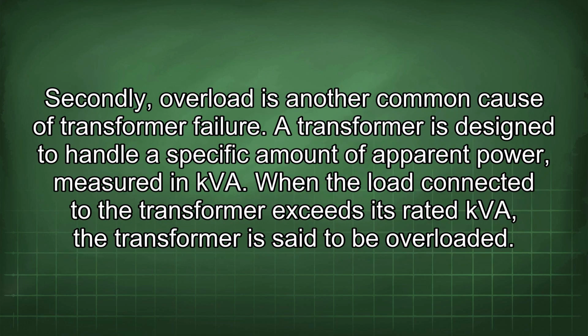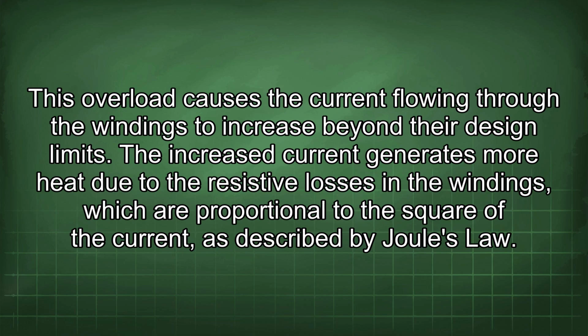Secondly, overload is another common cause of transformer failure. A transformer is designed to handle a specific amount of apparent power, measured in kVA. When the load connected to the transformer exceeds its rated kVA, the transformer is said to be overloaded. This overload causes the current flowing through the windings to increase beyond the design limits. The increased current generates more heat due to the resistive losses in the windings, which are proportional to the square of the current, as described by Joule's law.